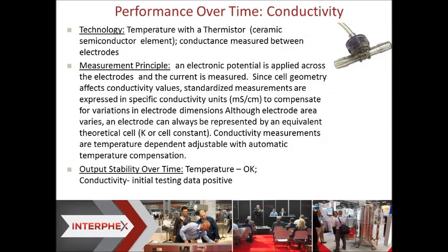As far as conductivity, it has the same temperature element, and the measurement principle is described here. Every conductivity cell has what's called a K factor, which is based on the fact that there are different geometries and surface areas, so it's standardized to what's called a K factor, and the measurements are standardized to millisiemens per centimeter. Conductivity measurements are very temperature dependent, so it's always temperature compensated, typically to 25 degrees, so you can do comparative measurements. And as we just showed, the temperature over time stability output is okay.